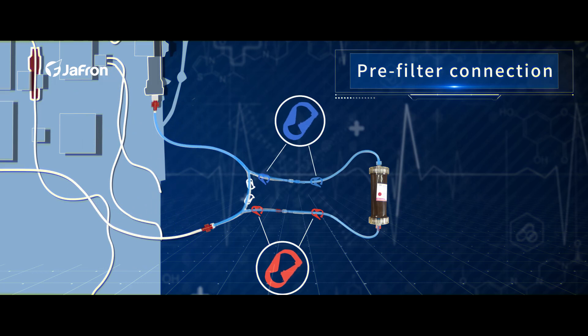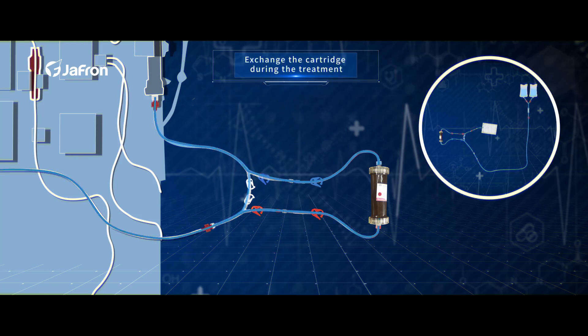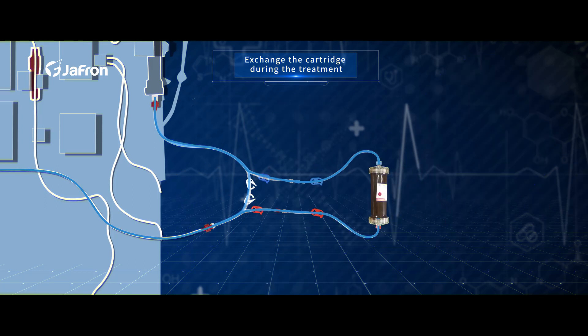To exchange a cartridge during treatment: Use normal saline to return blood from the cartridge. Prime a new cartridge and integrated bloodline set as previously described. Open the white clips, clamp the red and blue clips before and after the cartridge.